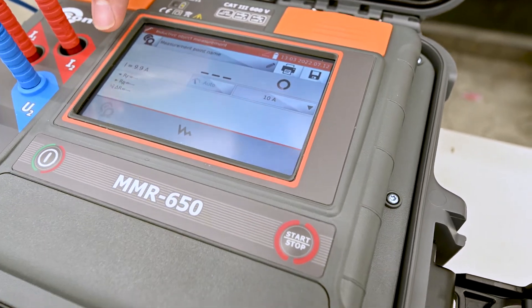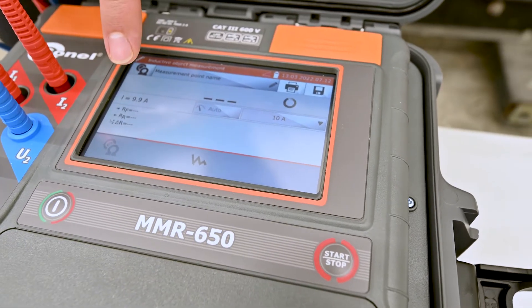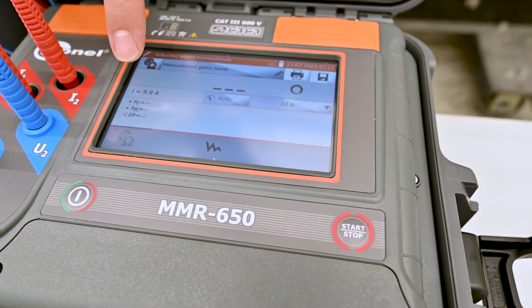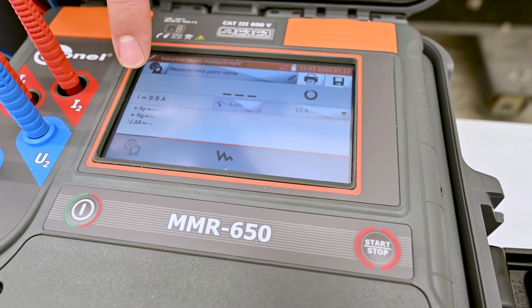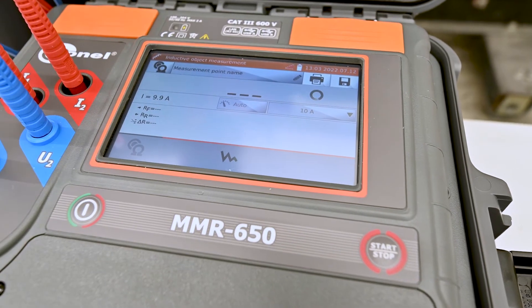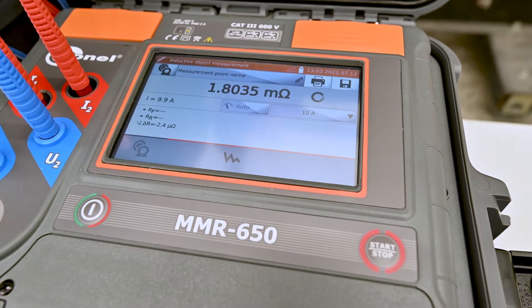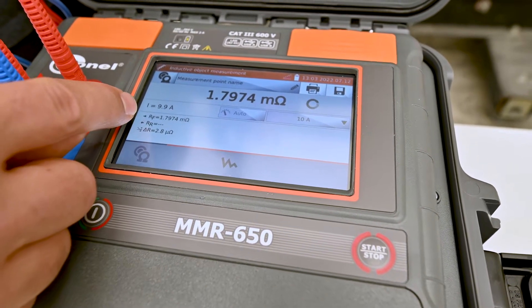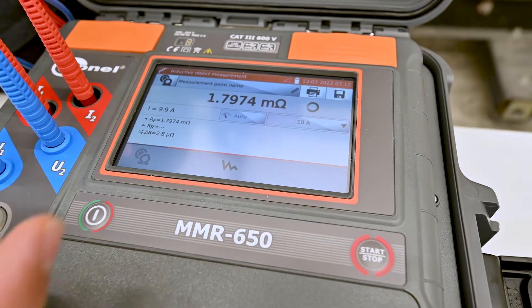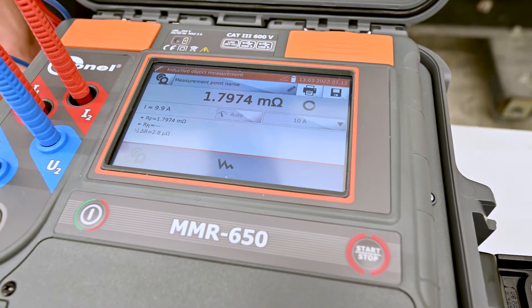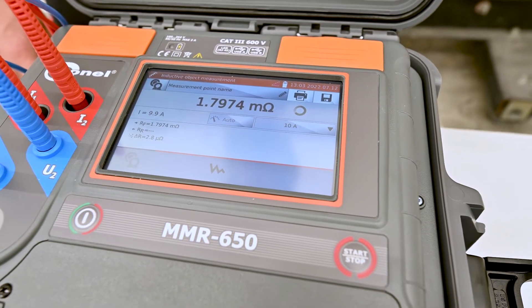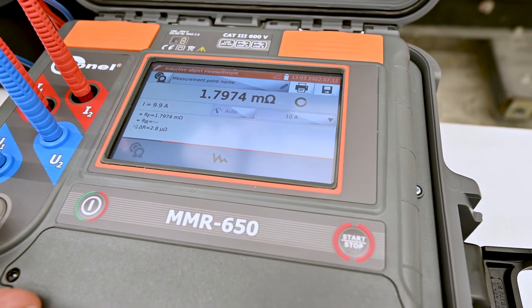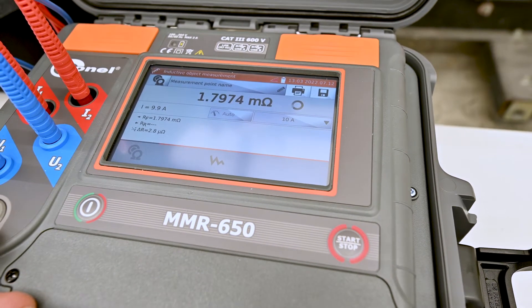You see the current will start to push, there it went, and we've got 1.7 milliohms. That's about what we expect for a low side winding. So let's repeat the measurement on the other two phases and compare them.